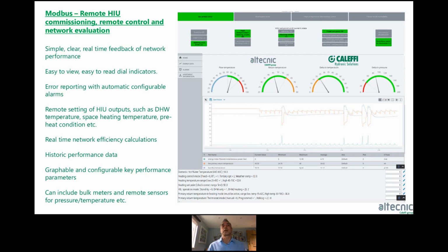The second one is Modbus connection and control. What I'm showing here is the head-end software from our Modbus. And what we've tried to do with this is simplify it. So you don't have to be an engineer to see what's going on. And that's why we have these very simple traffic light speedos, if I word them that way. And what you can see here, this is just a snapshot of one particular apartment. This would all be instantaneous live data from your project. And you could have 100 HIUs, 300 HIUs, doesn't matter, all connected. But this is looking here at an individual HIU.